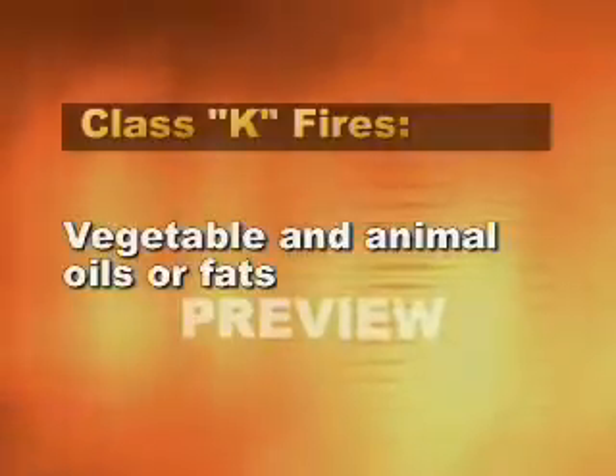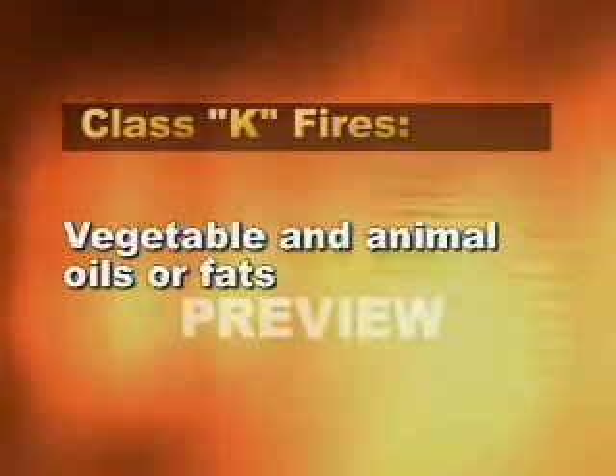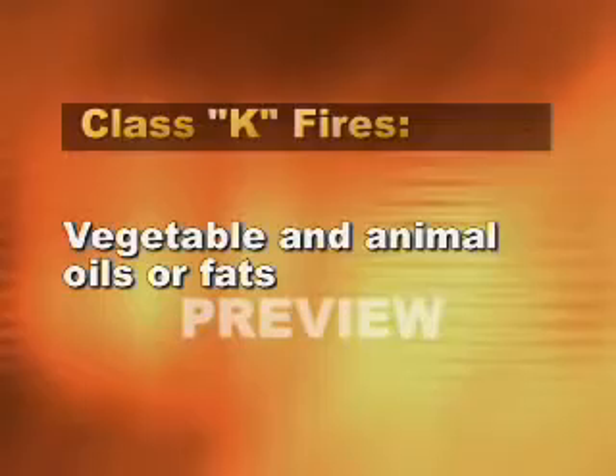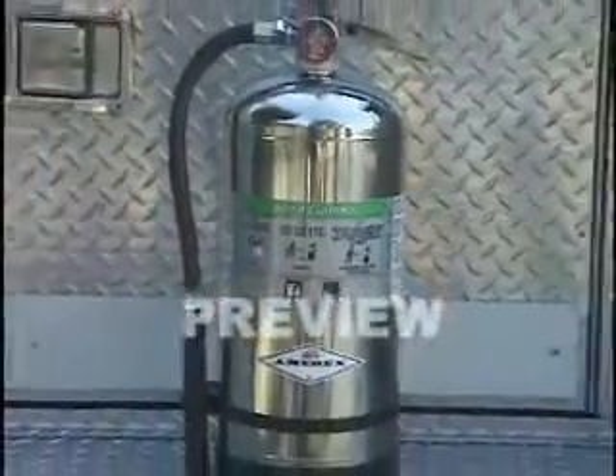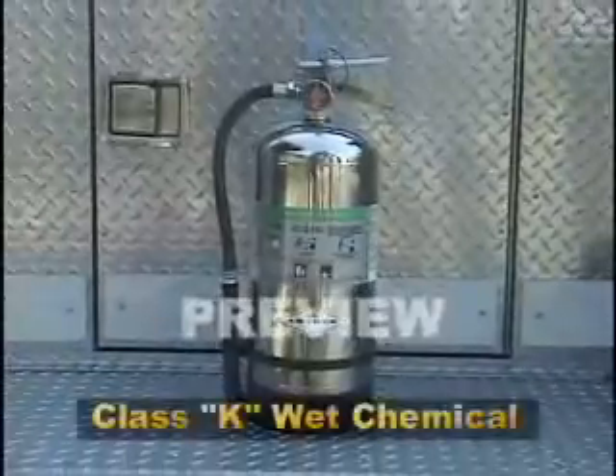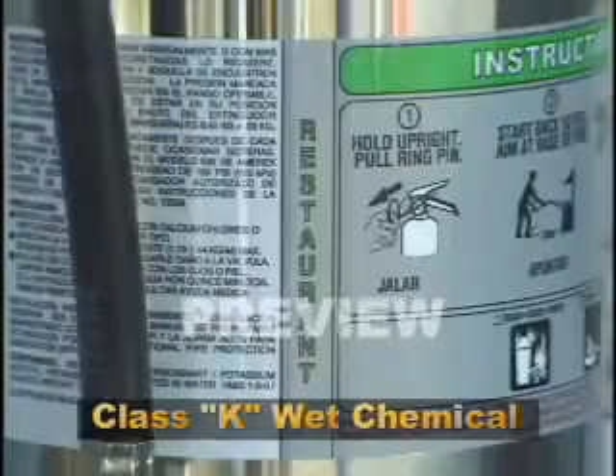Class K. Class K fires are fires in cooking appliances that involve vegetable or animal oils and fats. The only fire extinguisher that's effective on these fires is a wet chemical fire extinguisher with a Class K rating.